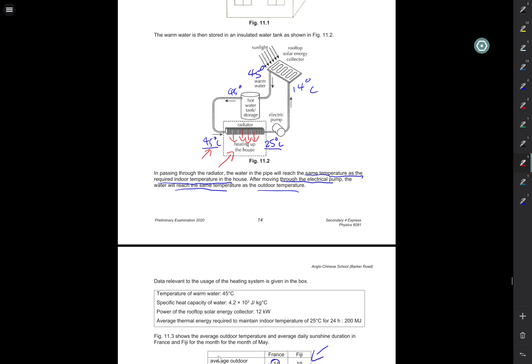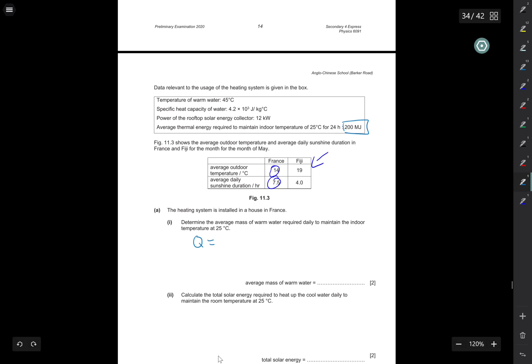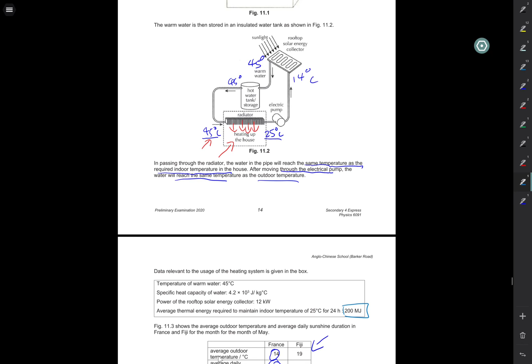Okay, so from here we are able to calculate the amount of warm water that is required, because this question says that the energy required to maintain the indoor temperature of 25 degrees for 24 hours, one day, is 200 megajoules. Therefore, we can use this equation, Q equals mc delta T. Why can we use this equation? Because as the water reduces its temperature, we are able to calculate how much heat is given off by the water. And in order for us to maintain 25 degrees Celsius, we will need 200 megajoules of energy. Now, how much mass we don't know, we leave it here. Specific heat is 4.2 times 10 to the power 3.